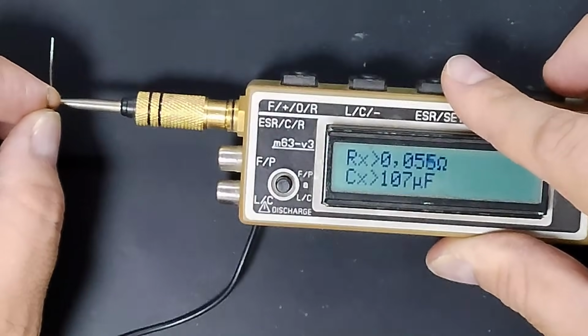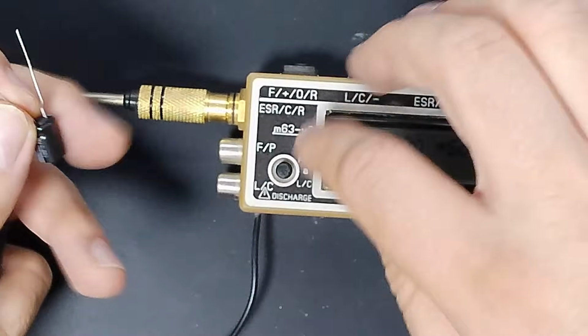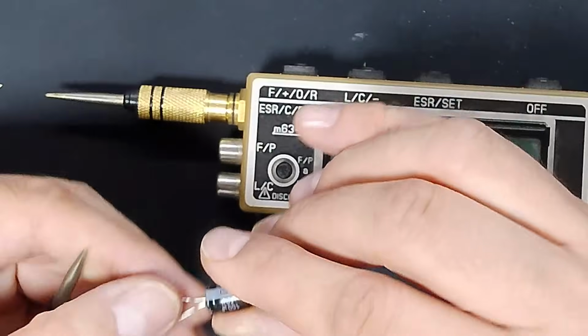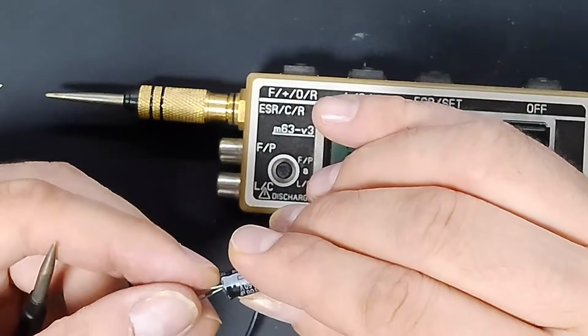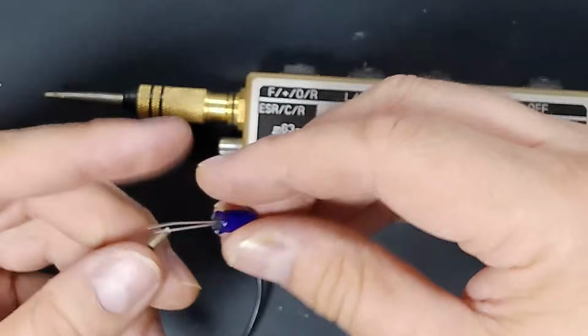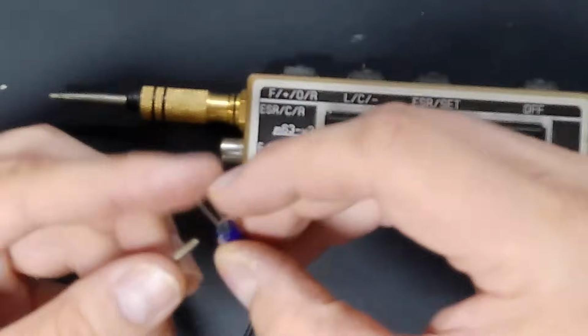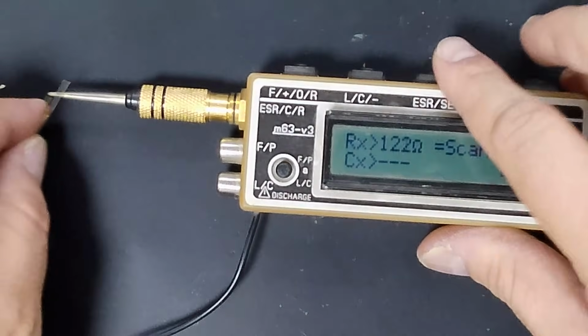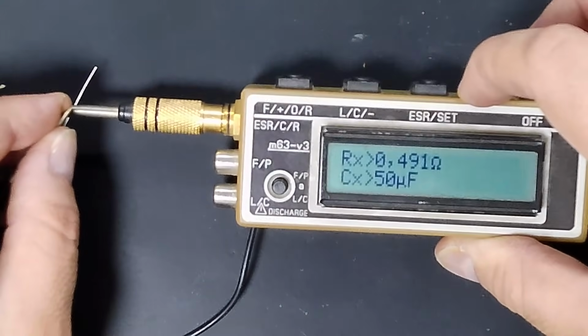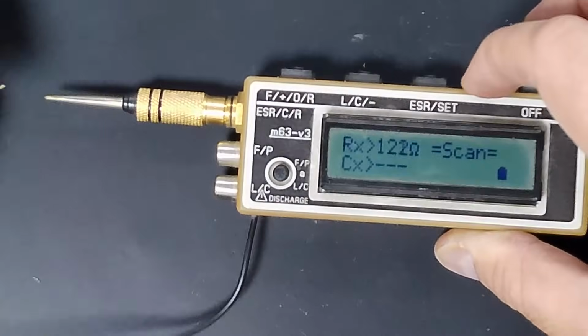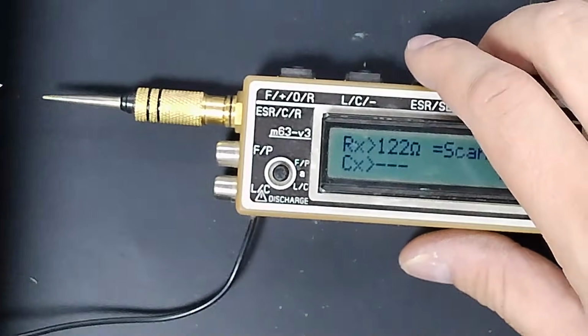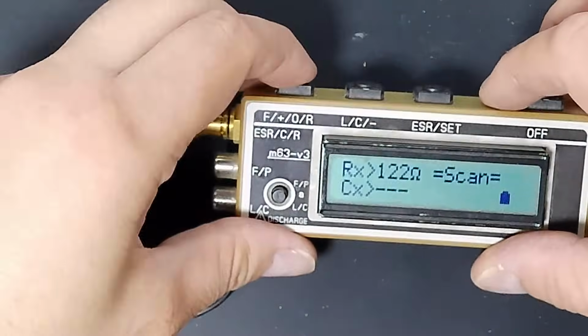107 microfarads. I'm not sure this one is calibrated. 107 microfarads seems a bit on the high side. 50. No, it seems to need calibration. How about the low resistance reading?